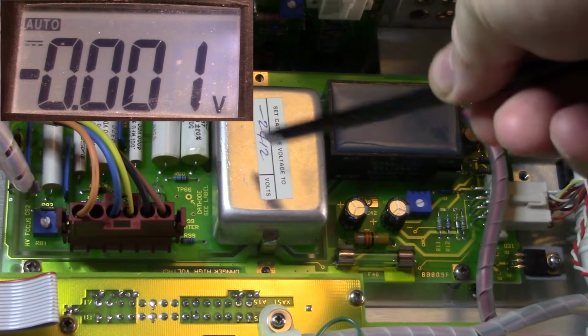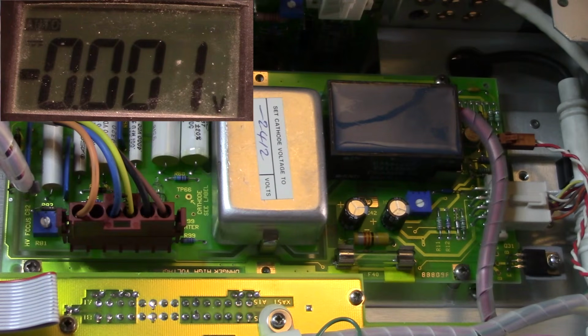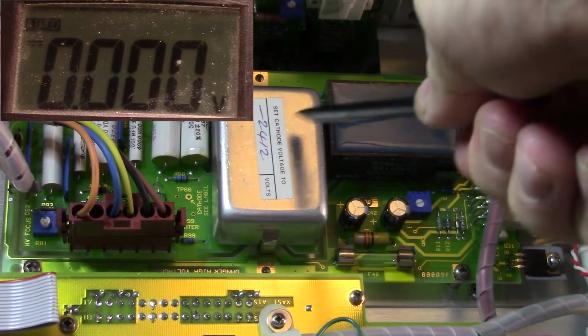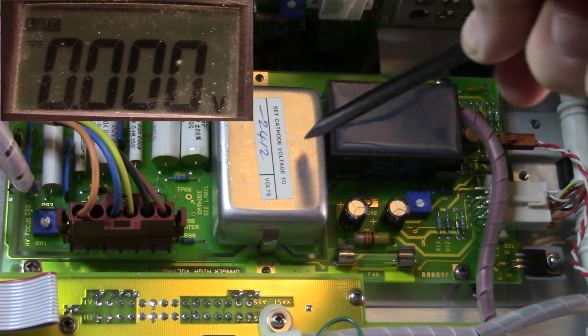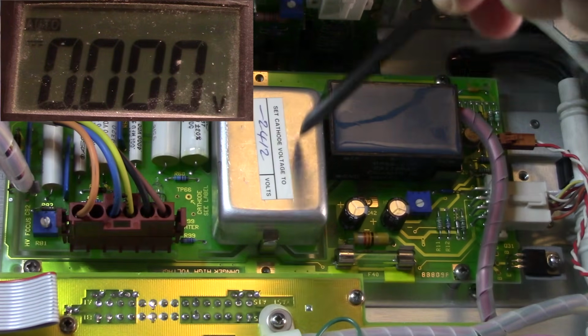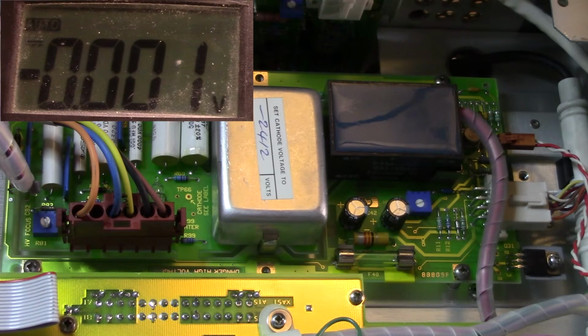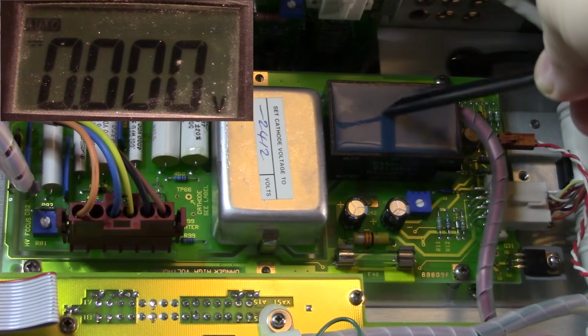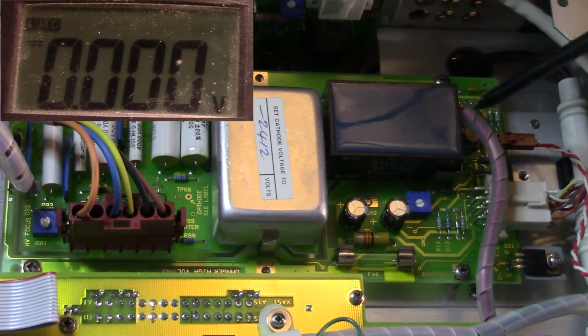This is the somewhat concerning part of the unit. This is the high voltage board. And you can see here that the cathode voltage is set to minus 2.4 kilovolts. And this is the high voltage multiplier, and coming out of this part here is 9.4 kilovolts. So it's mildly concerning poking around on that to see what's happening.